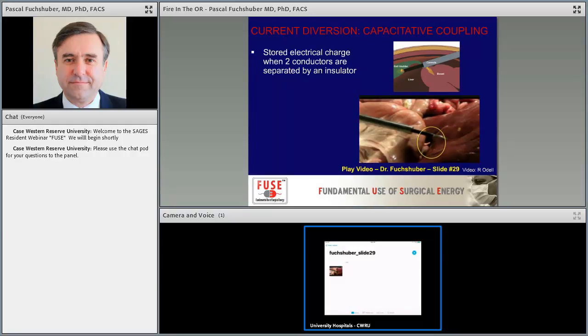This is the one current diversion that's a little bit more difficult to understand. It's called capacitive coupling. Basically, because we are using alternating high-frequency current in electrosurgical devices, every time you send high-frequency alternating current through an insulated electrical conductor, which is almost any laparoscopic device that you use, an electromagnetic field will build around that insulated device.